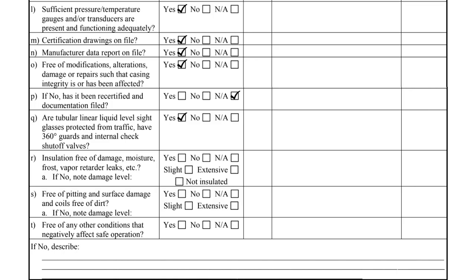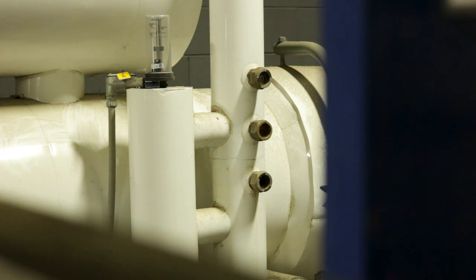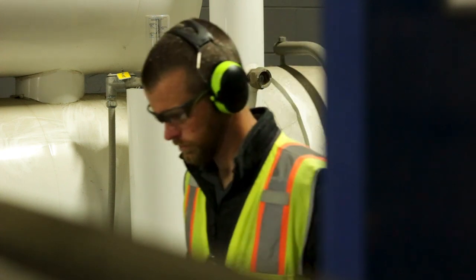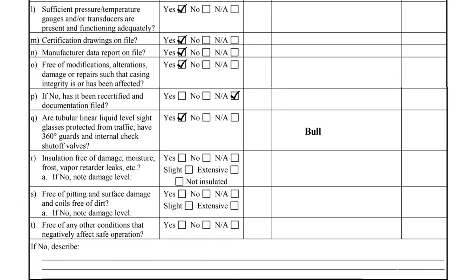Item Q asks the inspector to verify that the sight glass is adequately protected from traffic, equipped with 360-degree guards, and configured with internal check valves if the glass breaks. Bullseye columns like this example are exempt from having internal check valves per IIAR 2, so we suggest noting that in the comment column.